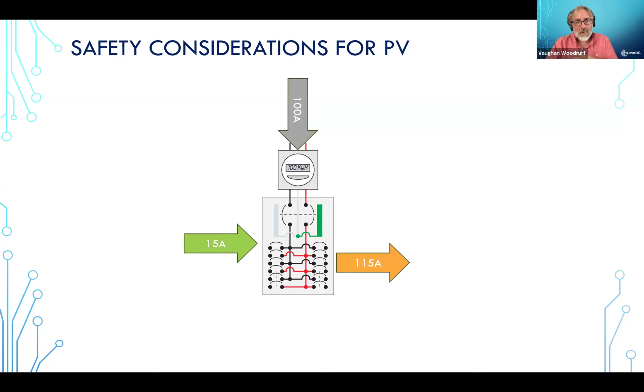Now, the question becomes, if you put that 15 amps up towards the top of the panel, you will have overheating in this kind of condition. And so that's why the code requires the breaker being in a specific position. And much as Stephan said, a lot of times folks don't know if the plug is the only plug on a circuit. Do you know where your outdoor outlet comes into your panel? Probably not. And there's a strong likelihood that it's not where it would need to be from a safety perspective if this has to meet the National Electrical Code and its strict interpretation today.